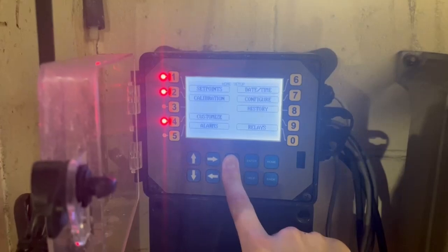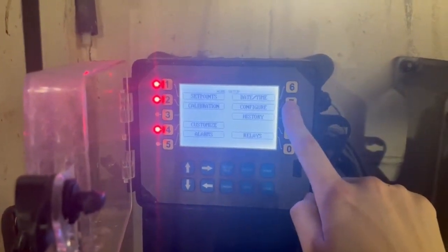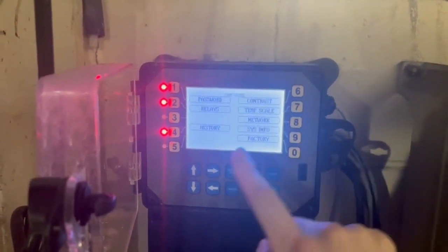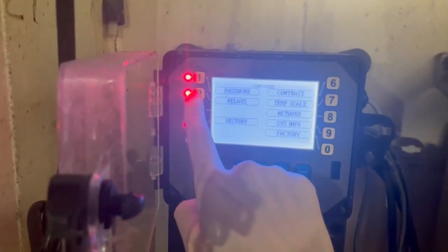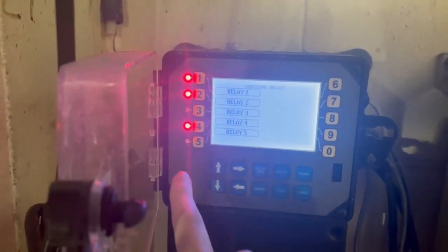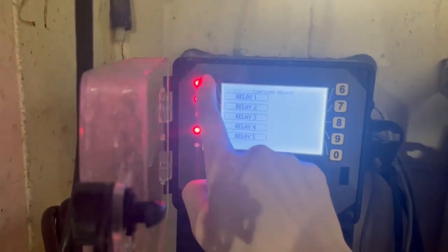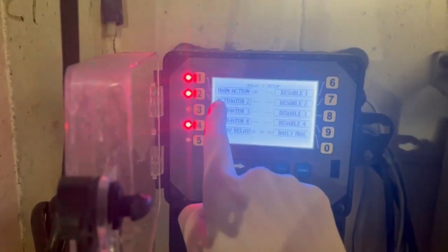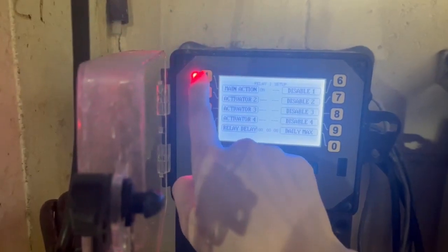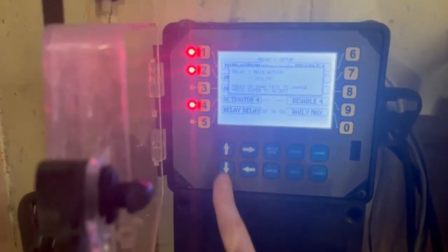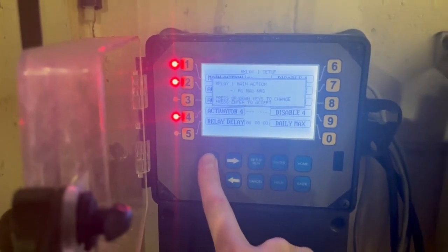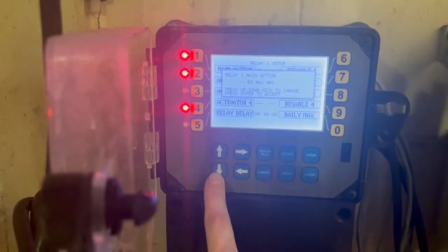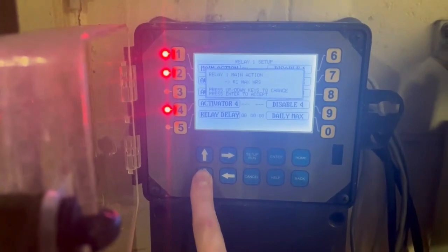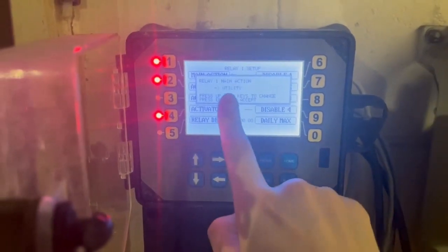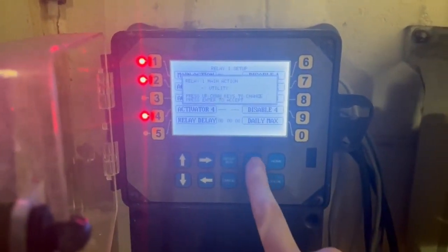Once you plug in and turn on your monitor, click Setup Run, and then you're going to click Configure. After that, you're going to press Relays. And then you're going to select Relay 1, and then you are going to select Main Action. A box is going to pop up, and you can use the up and down arrows to select different options. You're going to use these arrows until you land on the word Utility. Once done, press Enter.